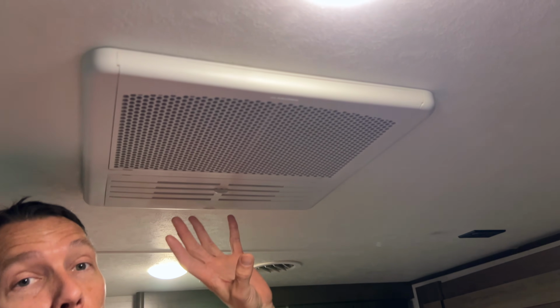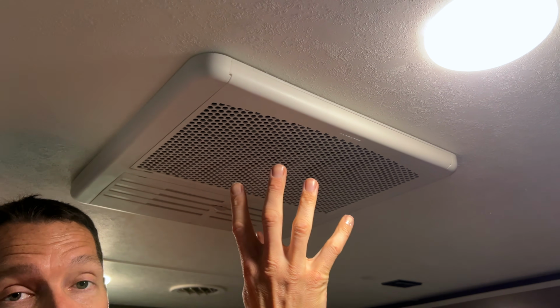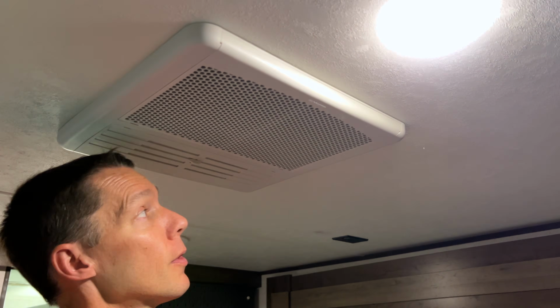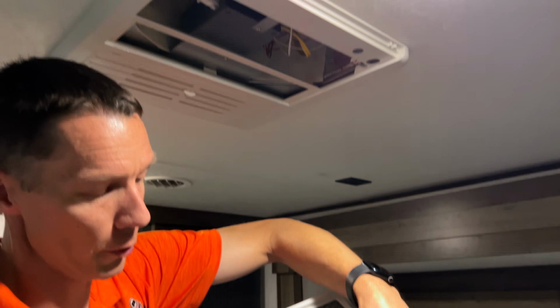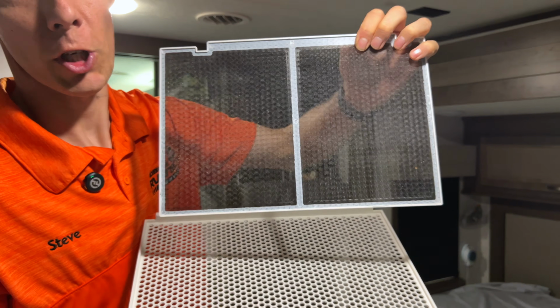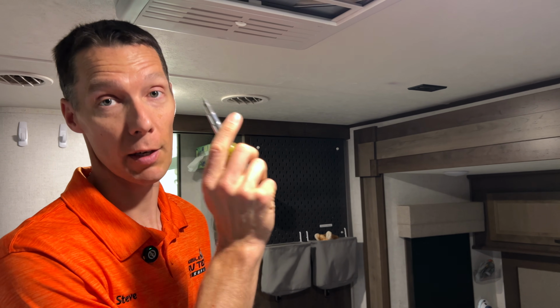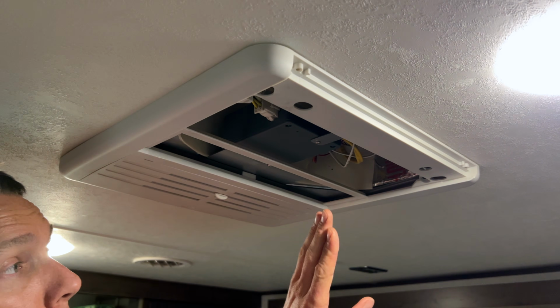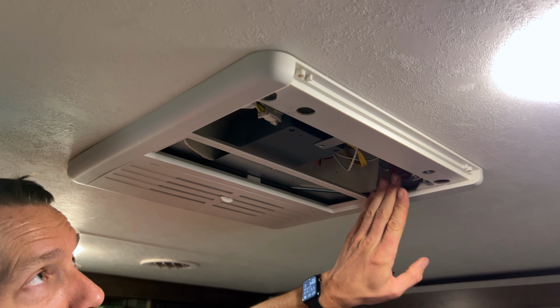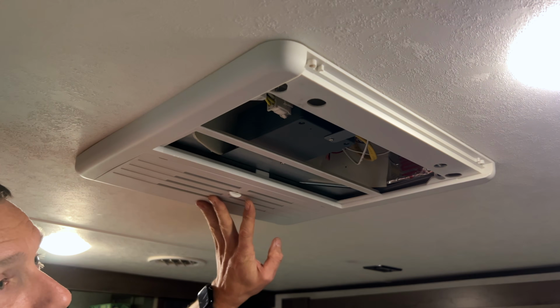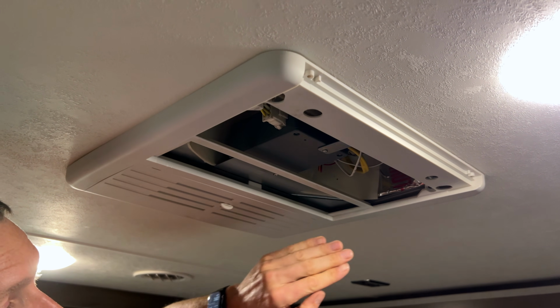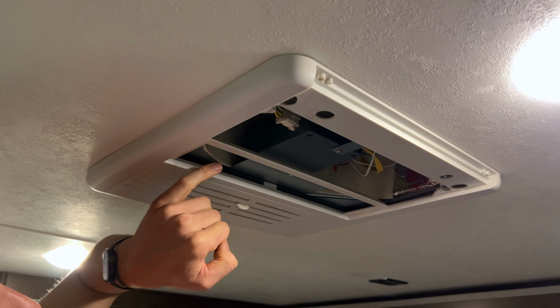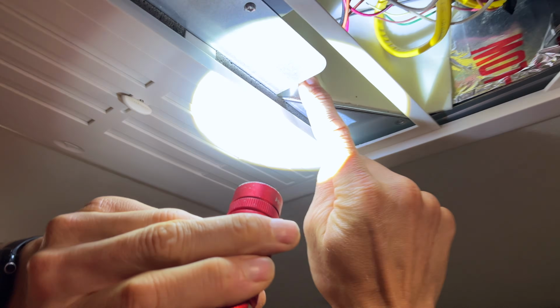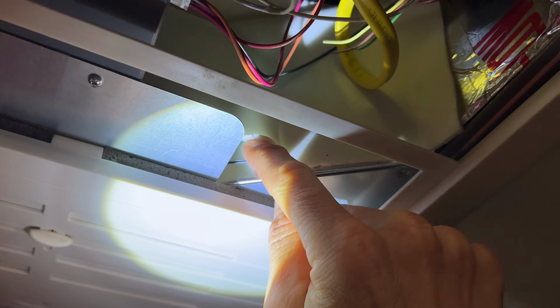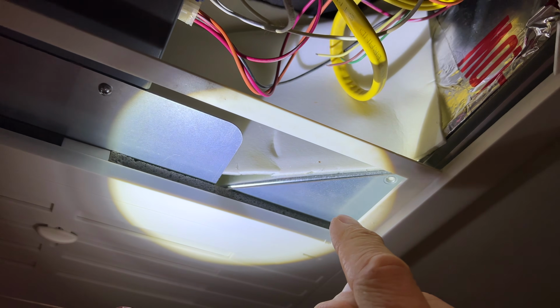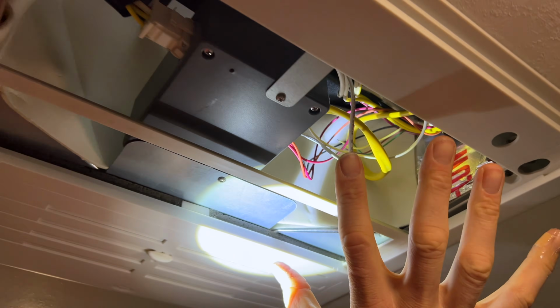Now on this style air conditioner, we have the big square on the inside. We'll pop off the intake filter side and look at the ductwork. So this will be your filter, just like the other one I showed you. Check to make sure that's clean. But what we're looking at inside of here is the actual ductwork itself. So this side is where the intake air comes in, going into the AC unit. And this side is where air comes out. And we're going to look at the divider between. That's the piece of metal or foam that's between there. If this is loose, air can get between the discharge side and the intake side, and it cycles around, doesn't come out your vents, and it short cycles through the AC unit itself.